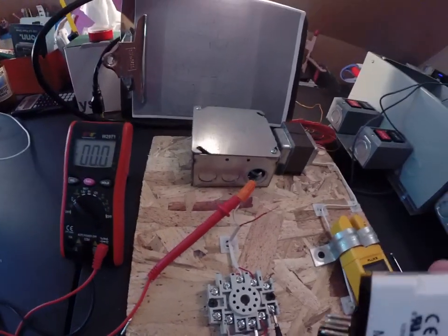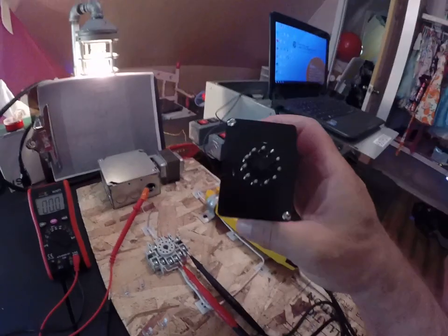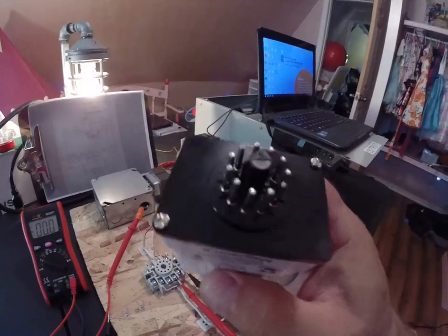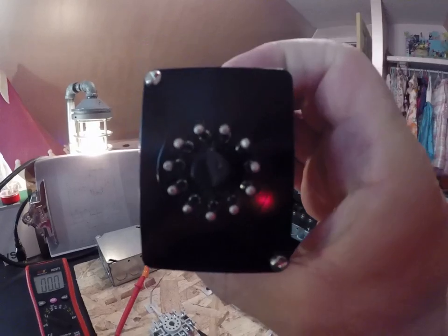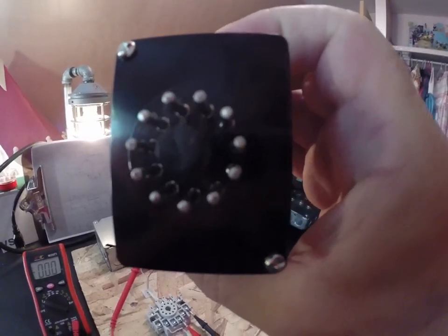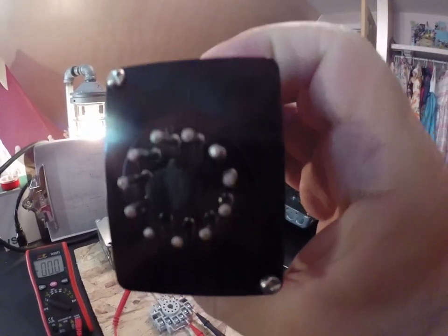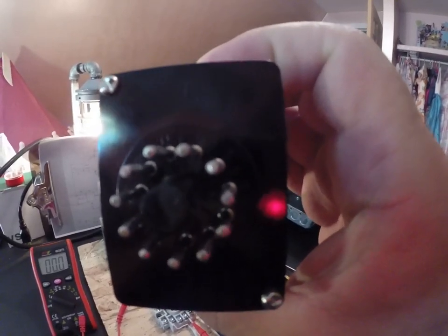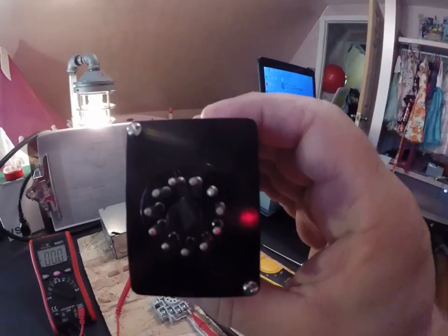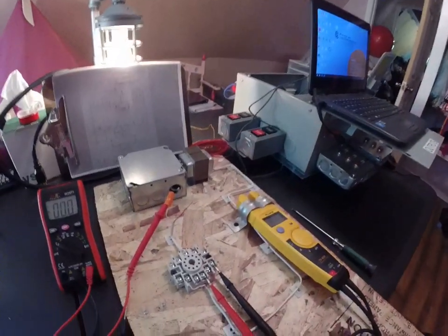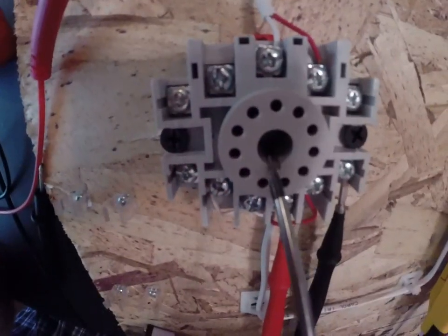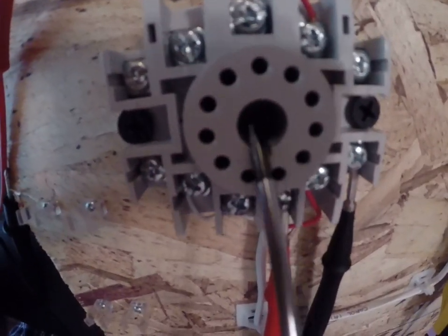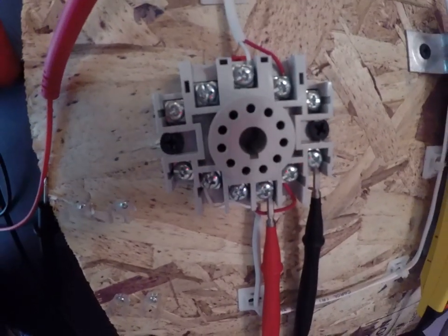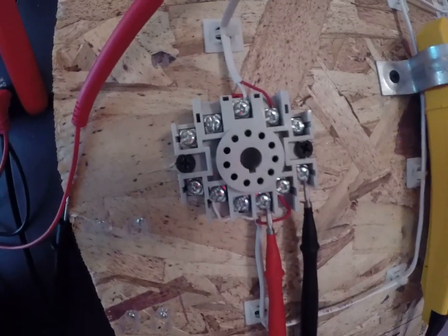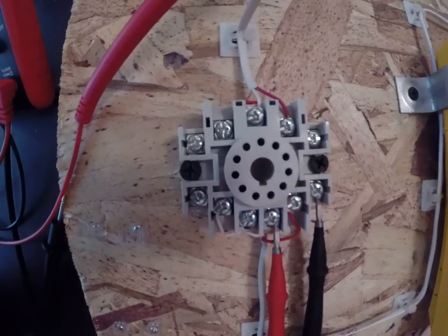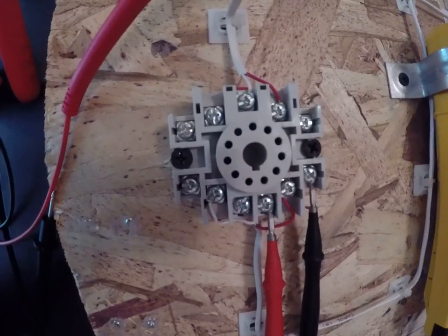When you plug the relay into its base, here's another reminder: on the bottom of these relays, in the middle of the pins, there's a plastic shaft that has a key. It's got a little nubby on that plastic, which means it only goes in the base one way. So you've got to look at that before you put it in the base and line it up with this key slot right here. This one's got 11 pins. It's not like the other gray base relays that we have that only have 8 pins.